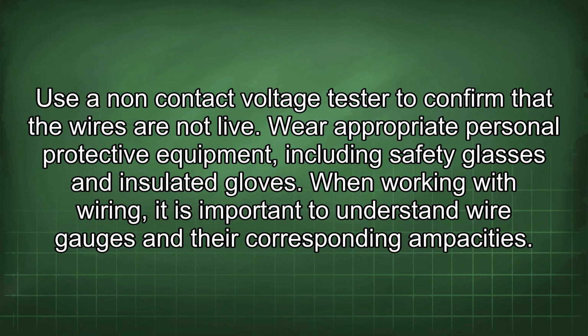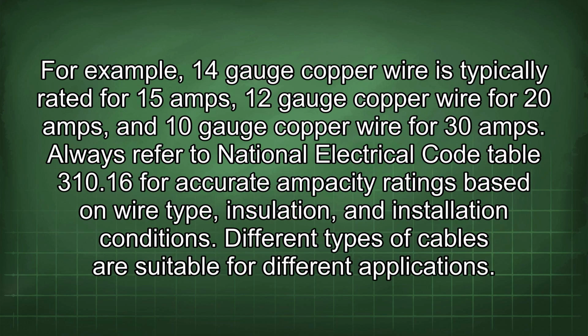When working with wiring, it is important to understand wire gauges and their corresponding ampacities. For example, 14-gauge copper wire is typically rated for 15 amps, 12-gauge copper wire for 20 amps, and 10-gauge copper wire for 30 amps. Always refer to National Electrical Code Table 310.16 for accurate ampacity ratings based on wire type, insulation, and installation conditions. Different types of cables are suitable for different applications.